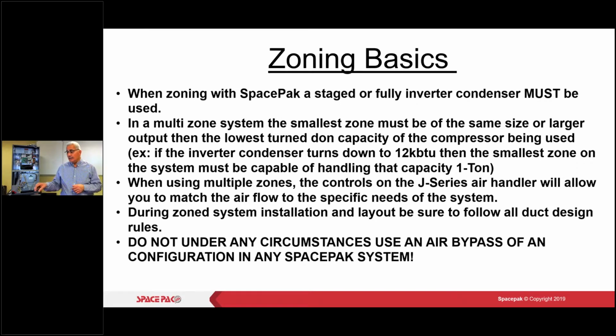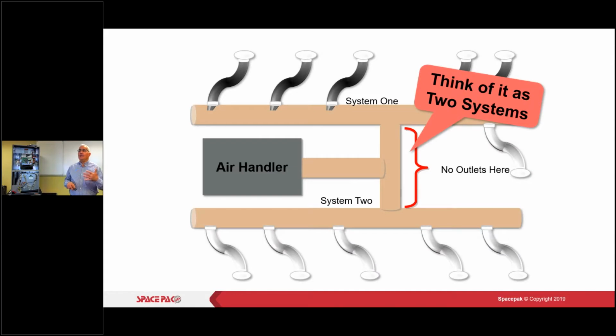So you can see here in a multiple zone, the small zone must be of the same size or larger output when the lowest turn down capacity of the compressor is being used. If the inverter compressor turns down to 12,000 BTU, that's 1 ton. The small zone on the system must be capable of handling the capacity of 1 ton. So again, if I'm going to zone in this type of configuration, think of it as 2 systems. So I've got a 60-40 on either side, and I'm thinking this is 2 systems.